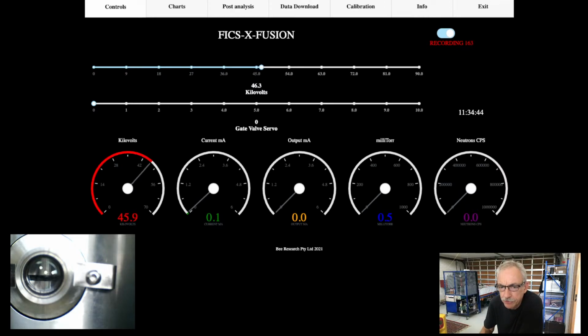I've set it to about 50 kilovolts. So we go here to 50, and then we can see, okay, at 53 kilovolts, its current is draining through the Zener, so it's coming in through the power supply on the green dial, and it's going out through the Zener on the yellow dial. So we now confirm that the Zener is working, and the breakdown voltage I've set it to is 50 kilovolts, pretty much exactly right. It's pretty amazing considering there's hundreds of Zeners. You can see at 52 it just comes straight out there and goes. Okay, so we're all good with that.